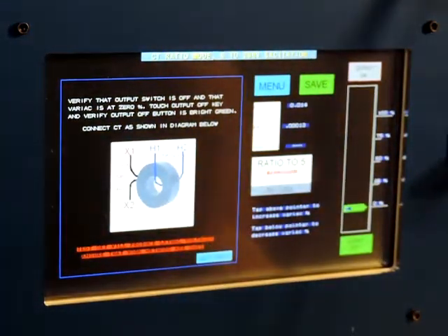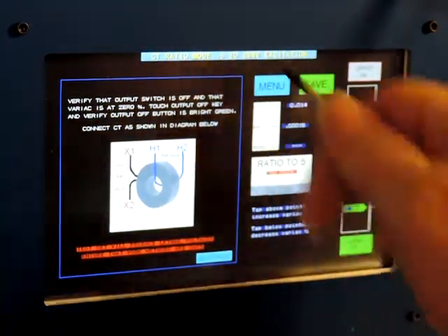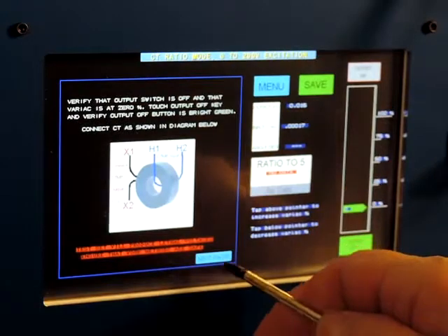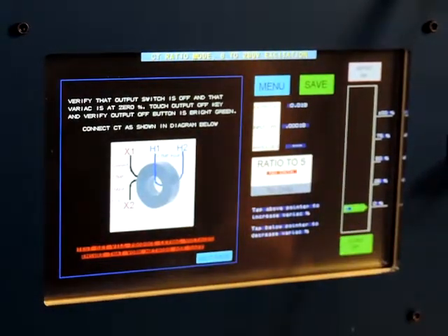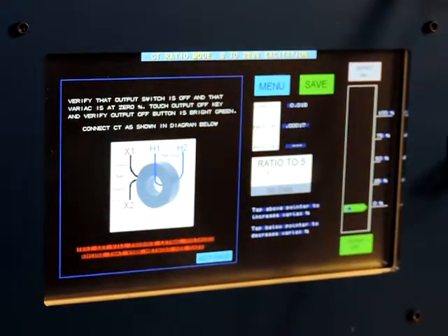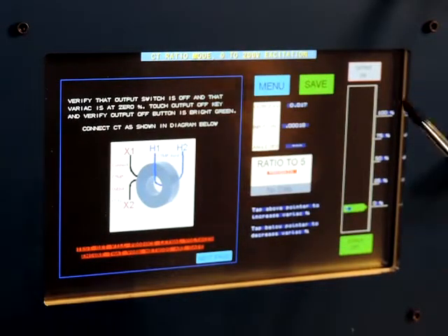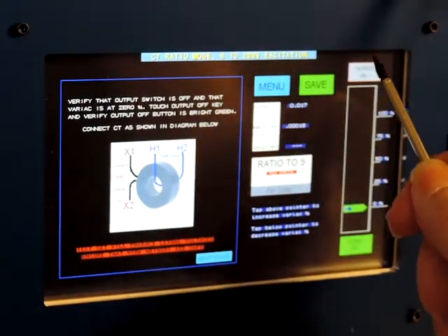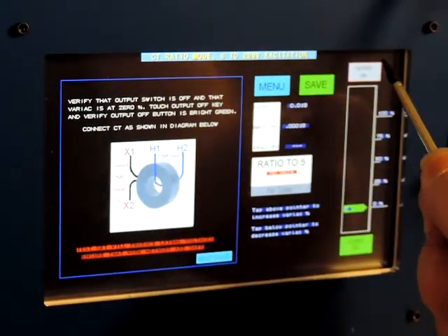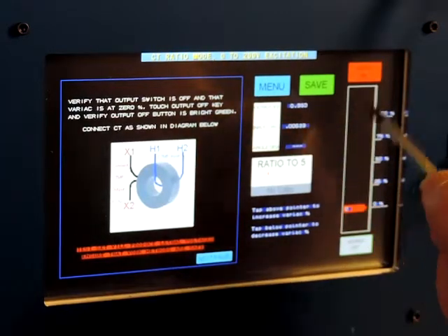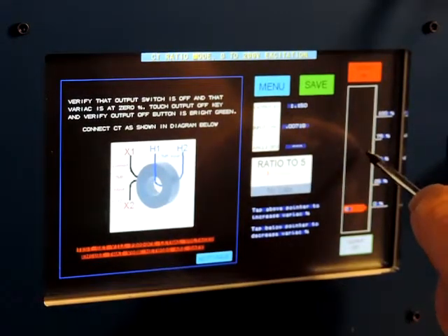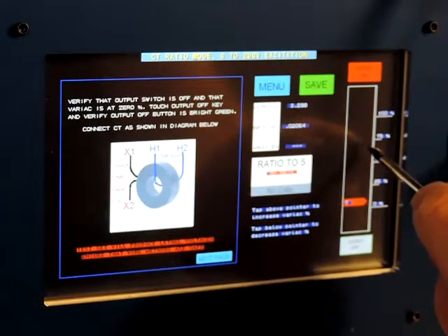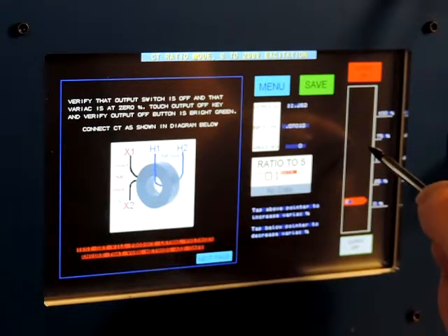Now I'm at the ratio page. There are instructions on the screen — you can page through them to see how the test set works and how you would connect it to test a current transformer. The first step is to turn the output on by tapping the output-on button on the screen, then raise the output voltage.